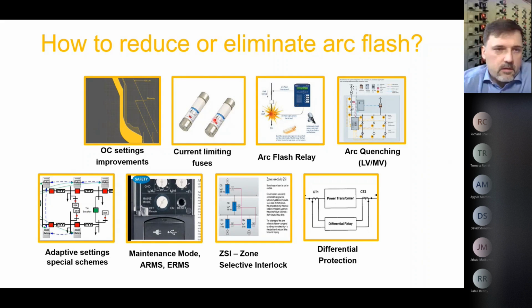The next thing, very similar to this one, is current limiting fuses. If your system is mainly made with fuses for protection, you might have a look at current limiting fuses. Not all fuses are current limiting, which is why I have it here. And they will significantly reduce the arc flash energy.